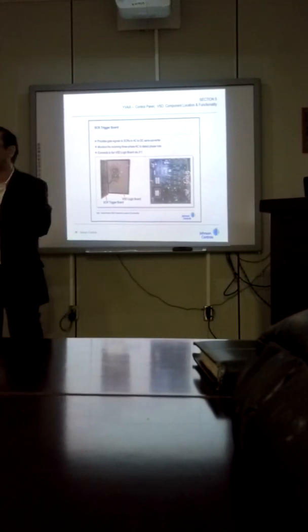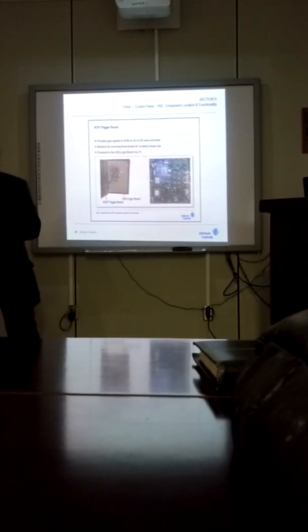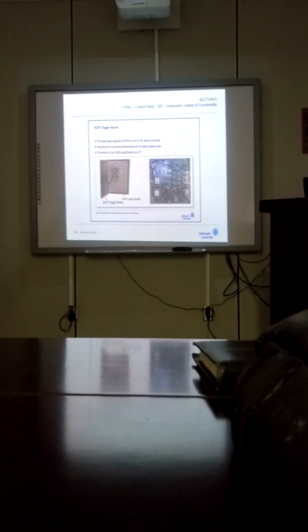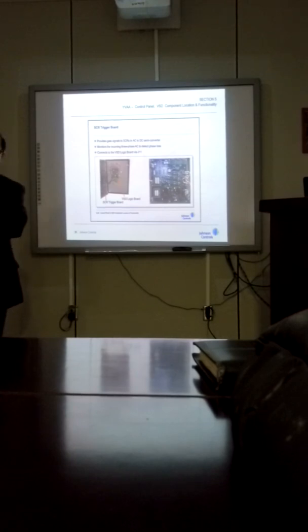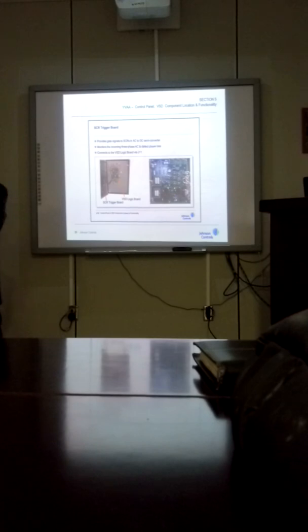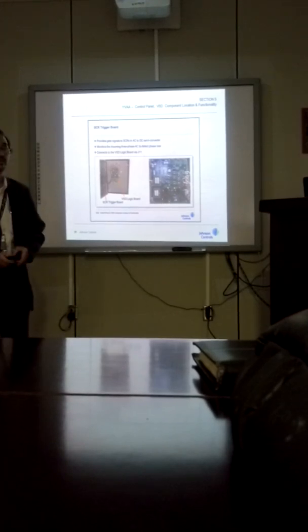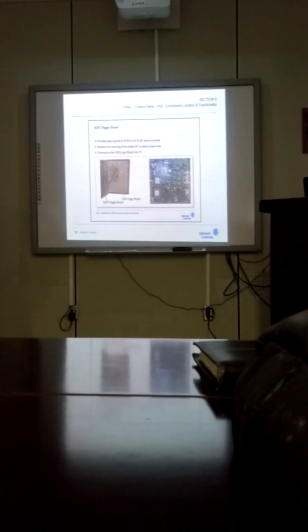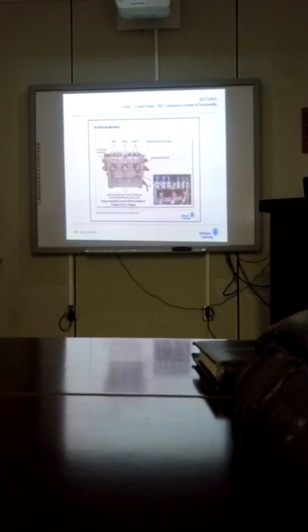We have to find out why. We have to check this one on the side when we go there. So from that we can also determine why it's fluctuating. Maybe you need to adjust your substation or MCCB. Maybe the length of wire is too much. So you have to provide a trap for checking, the Megger and all this. Okay.